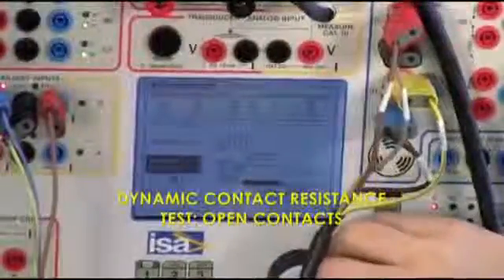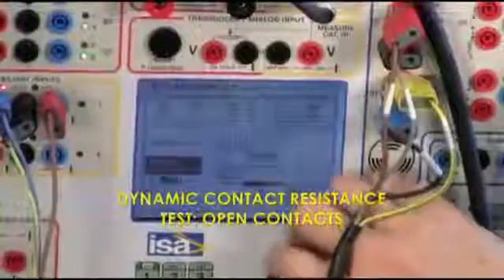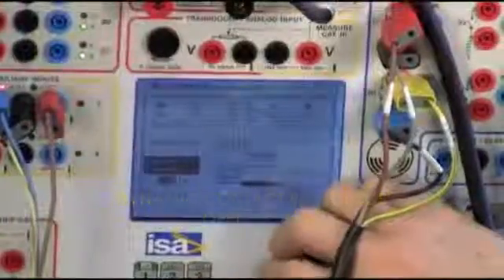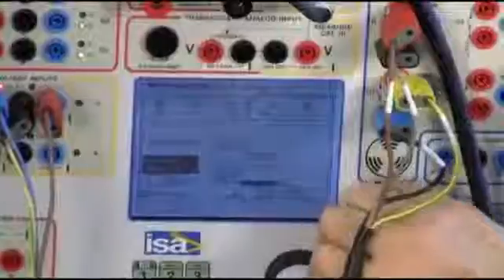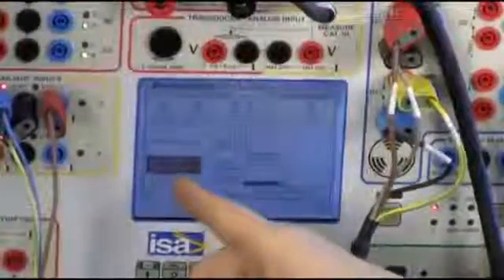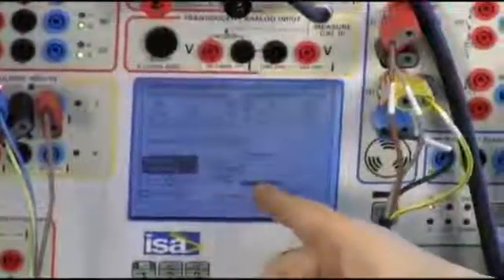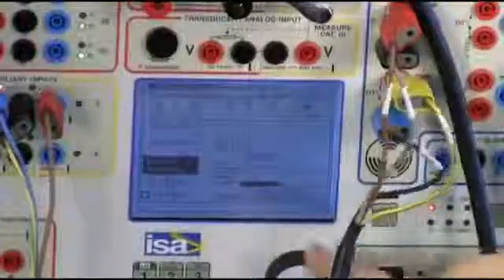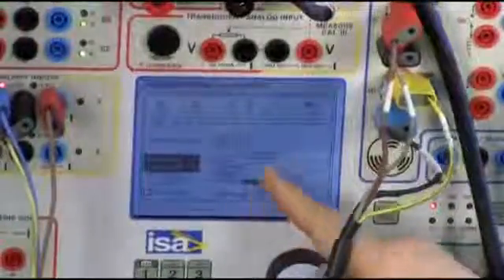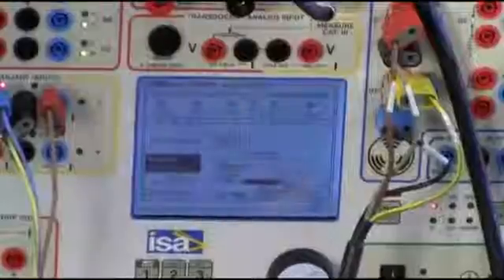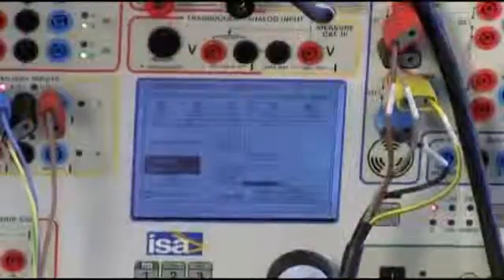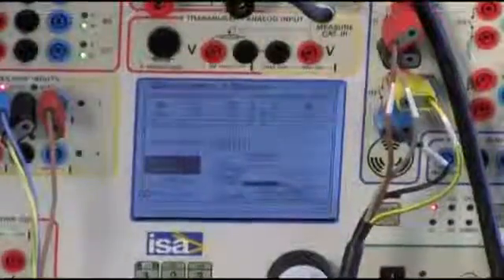So what we have to do now is to program the nominal operation time, that is 43 milliseconds, okay? Taking into account this, we will generate the current shortly before the actual opening, so that we are injecting current when the contact is actually opening.